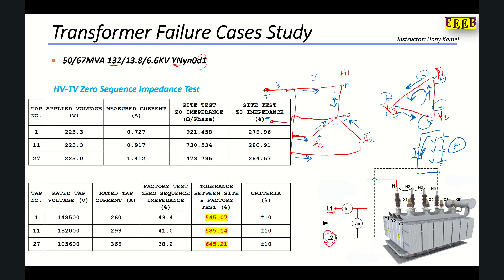The total current from the three phases sums to 3I, returning through the neutral point. Applying 223 V at tap 1, the current is 0.727 A and the ohmic impedance is 921 ohms. The zero sequence impedance percentage shows a significant error compared to the factory value, exceeding acceptable criteria. The same issue is found at tap 11 and tap 27, confirming that the zero sequence impedance test also failed — proving there is a problem in this transformer.